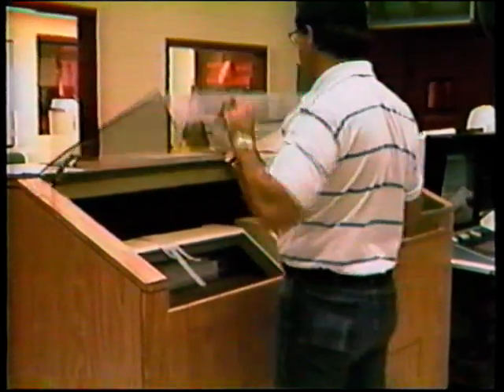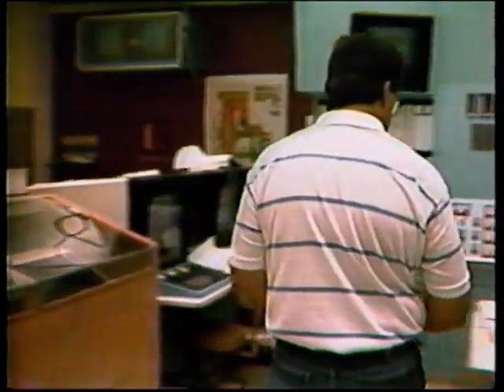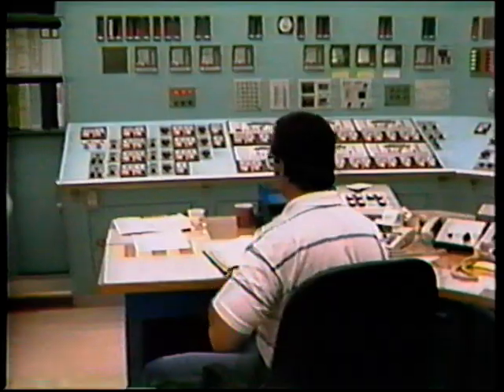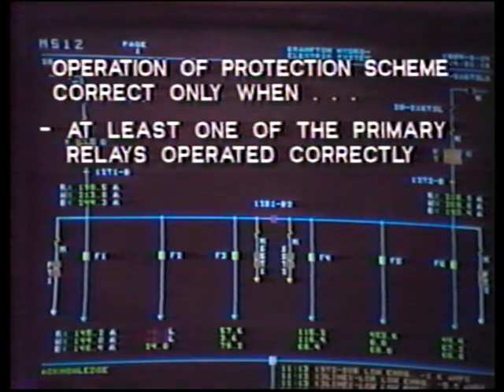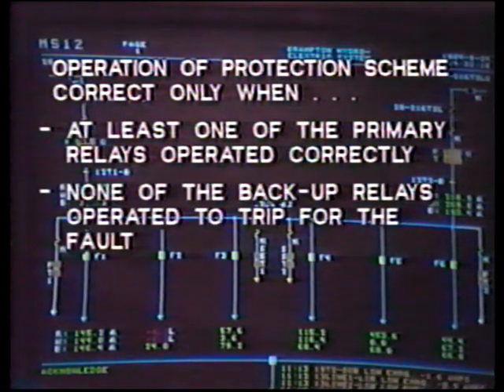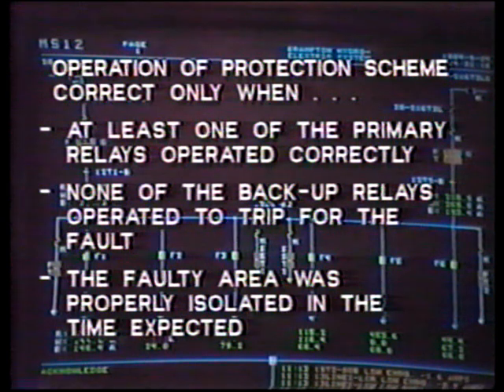In most utility companies, operation of the protection scheme will be classified as correct only when the following conditions have been met. That is, 1, at least one of the primary relays operated correctly. 2, none of the backup relays operated to trip for the fault. And 3, the faulty area was properly isolated in the time expected. Obviously, knowledge of all conditions on the system at the time of relay operation must be known. This will bring to light, in some cases, incorrect operation of the protection system. This could cause, perhaps, isolation of a no-fault area, or even worse, a failure to isolate the trouble area.